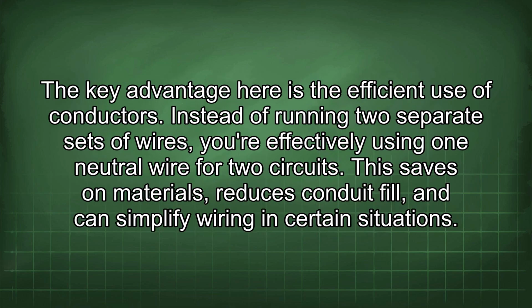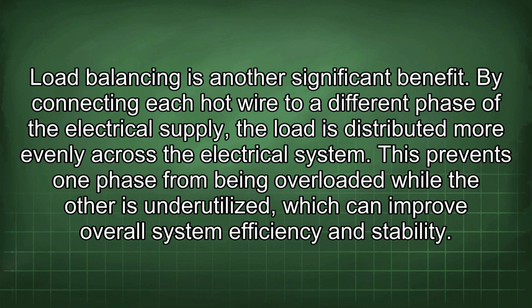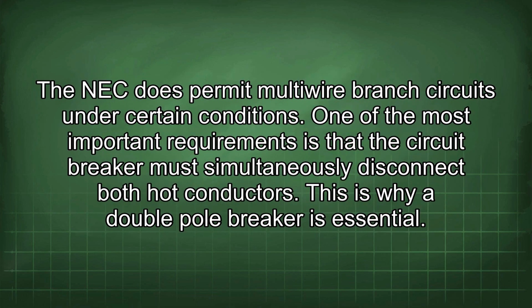The key advantage here is the efficient use of conductors. Instead of running two separate sets of wires, you're effectively using one neutral wire for two circuits. This saves on materials, reduces conduit fill, and can simplify wiring in certain situations. Load balancing is another significant benefit. By connecting each hot wire to a different phase of the electrical supply, the load is distributed more evenly across the electrical system. This prevents one phase from being overloaded while the other is underutilized, which can improve overall system efficiency and stability.